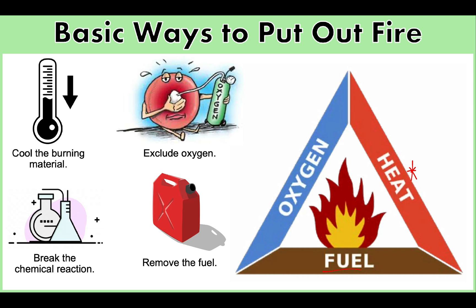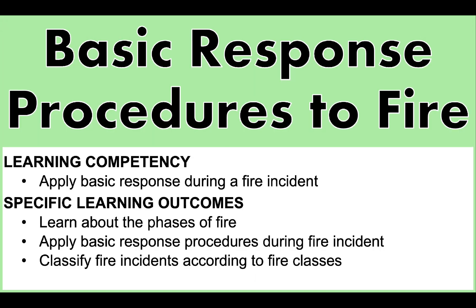The last part of the fire triangle is oxygen. Ambient air is made up of approximately 21% oxygen, and most fires require at least 16% oxygen content to burn. A fire ignited in an area with little oxygen will support only a small flame. If oxygen is suddenly and rapidly added to a nearly suffocated fire, the re-oxygenated air will quickly ignite, creating large and dangerous flames known as a flashover or backdraft. This will be further discussed in the next video on basic response procedures to fire.